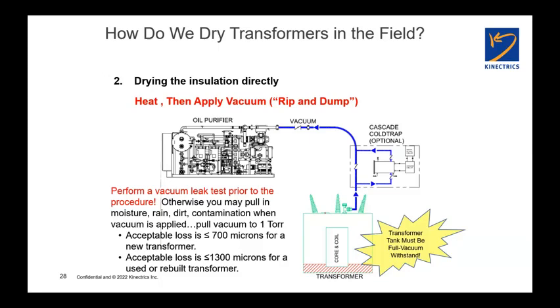And this is where the problem comes, because as the water starts to come out of the paper, it gives up its latent heat of vaporization, which for water is a very high number. And so very quickly, the temperature will start to drop. Believe it or not, I've seen cases where so much heat is given off through the latent heat of vaporization of the water that ice actually forms in the core coil assembly. So you have to be very careful how long you pull vacuum. You have to monitor the temperature constantly to make sure that you don't get into a region where icing is going to happen. And again, this is because we're not applying heat and vacuum at the same time.